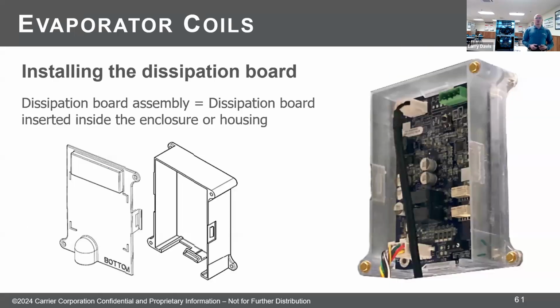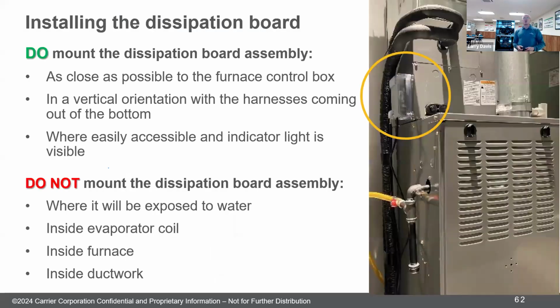That dissipation board on the evaporator coils, it comes in an enclosure with a wire harness that runs from the board to the sensor and a harness that runs from the board down to the furnace to wire it up. Make sure that enclosure is installed upright where the harness comes out the bottom. You just don't want moisture, things like that to get in there. So that's what we're talking about here.